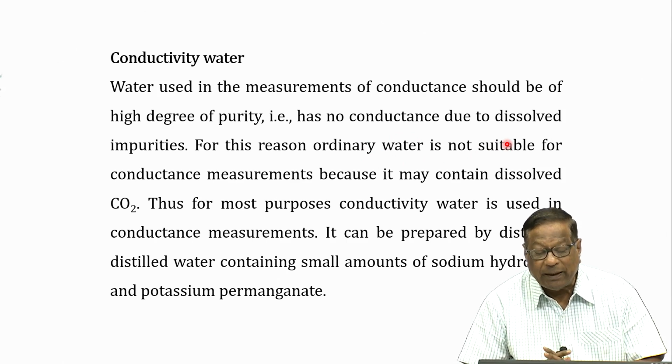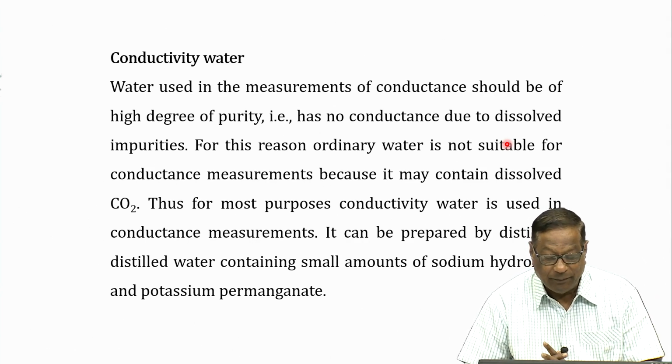For this reason, ordinary water is not suitable. You cannot store a conductance electrode in normal tap water or well water or sea water or any of the waters, because it may contain dissolved CO2. Apart from the salts, it should not have CO2 also.